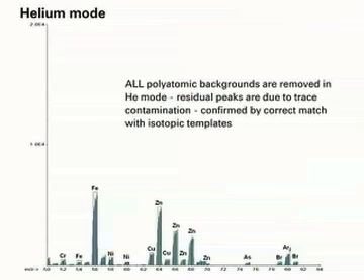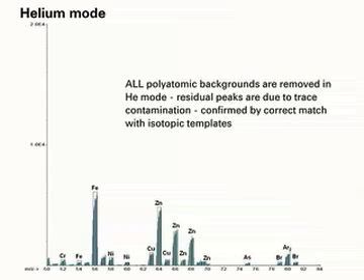Now watch what happens when helium is added to the cell. All matrix-based interferences are removed. The remaining elemental peaks are due to parts per billion level contamination in the matrix. This is confirmed by the correct isotopic template fit.